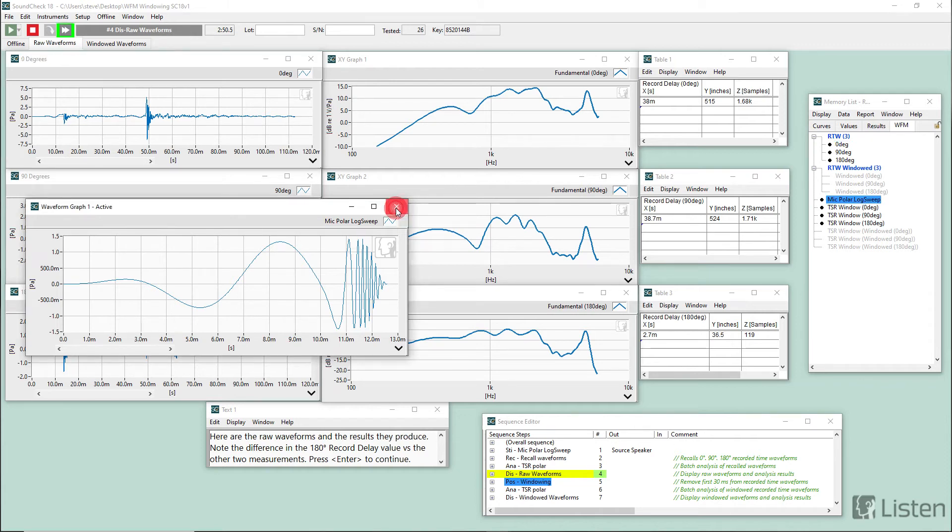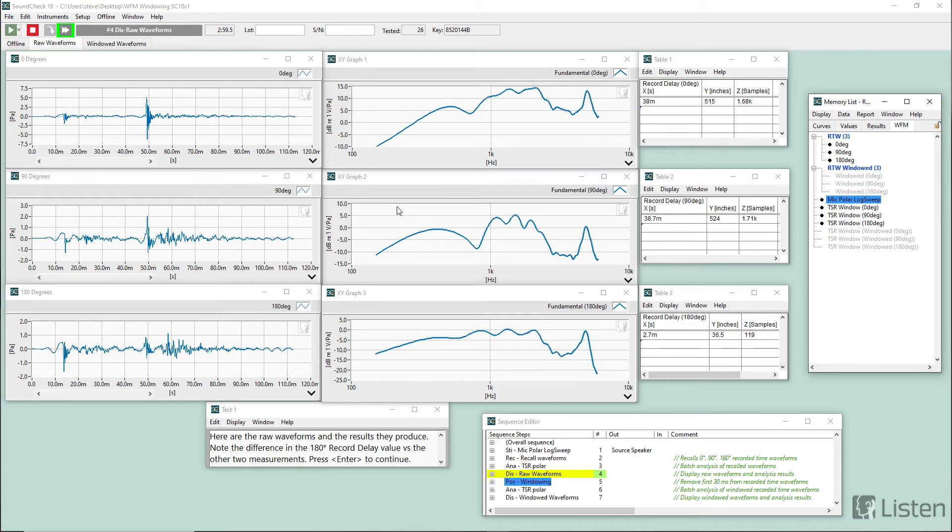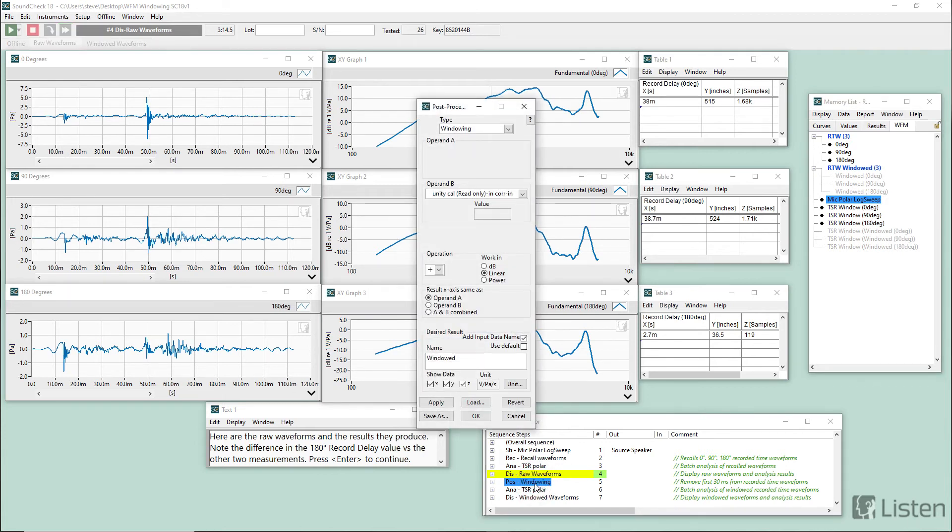So this was the challenge. What could we do to help the customer get accurate measurements at every degree of rotation? And what we came up with was windowing the waveform so we could just completely exclude the leakage from the analysis waveform.